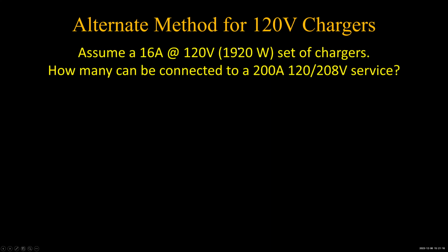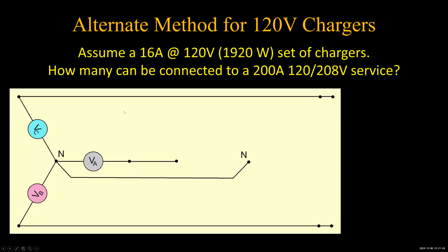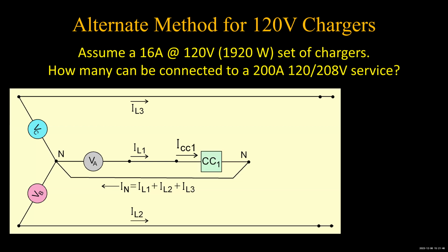And of course, the alternative method is how many can you connect to 120? You can just draw a circuit here and show that you connect. You got line 1, 2, and 3, and neutral current. And the neutral is the sum of the 3 line currents. If you notice, the neutral current's going back to the neutral point, and the line currents are all coming out. And of course, these are out of phase, so they can sum up to whatever. So let's see what they're adding up to.